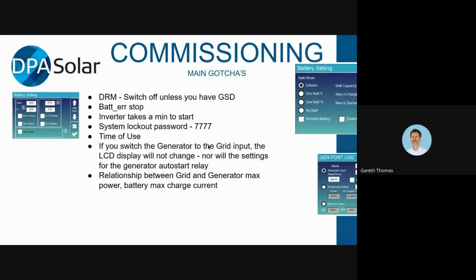So this is just the main takeaways. We're pretty much out of time, but the main takeaways from my experience with these inverters so far: the DRM, you've got to switch that off unless you're using a GSD device. And the battery error stop, make sure that's switched on when you're using a managed battery.